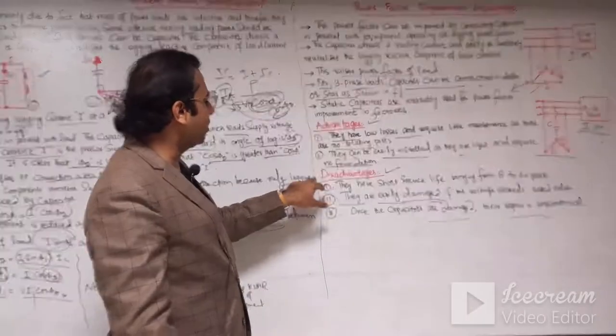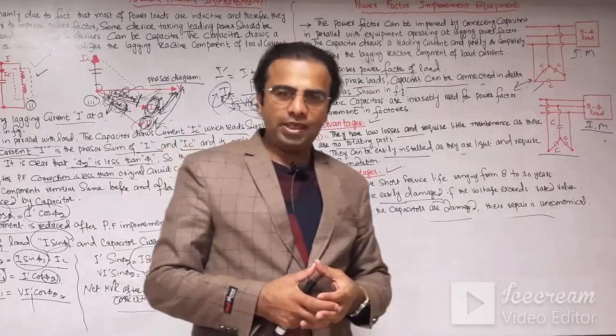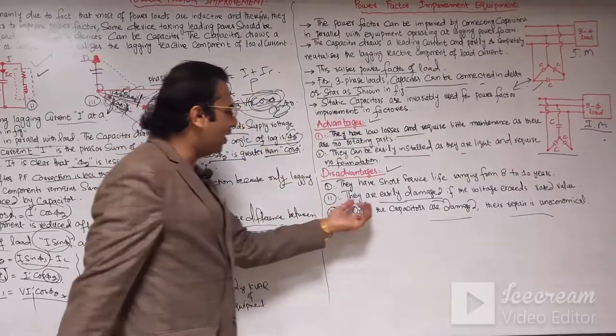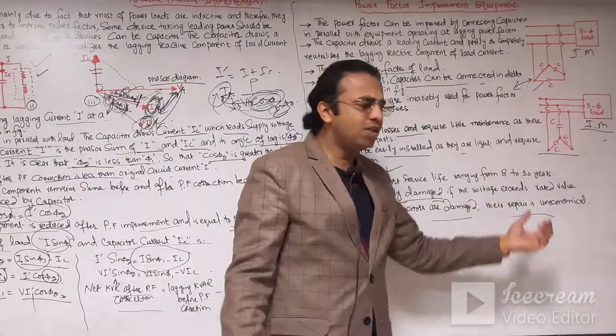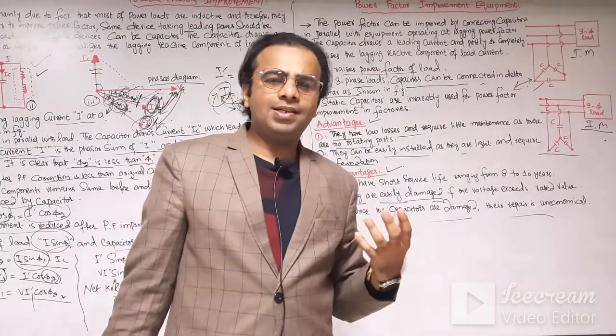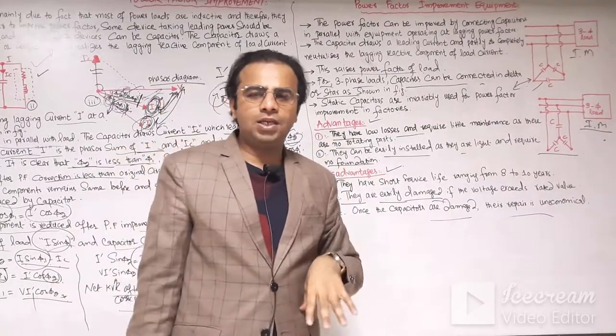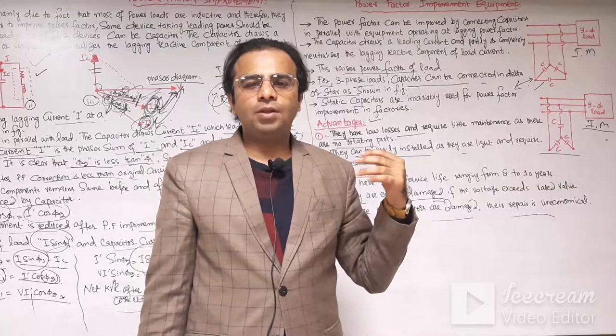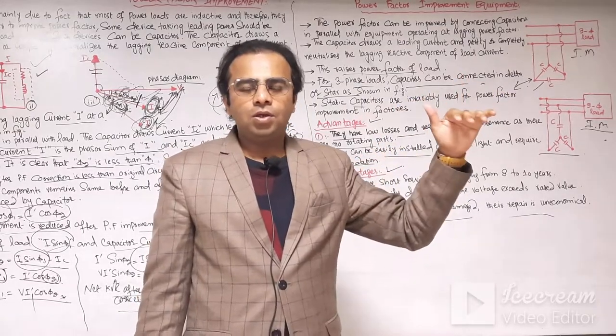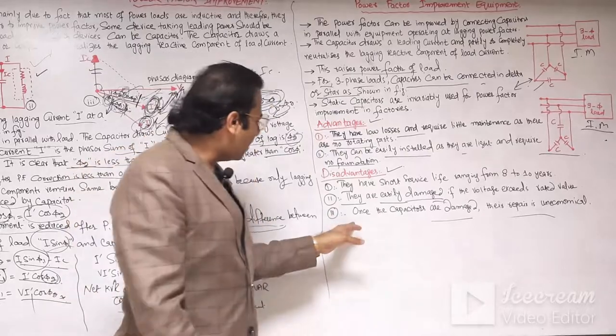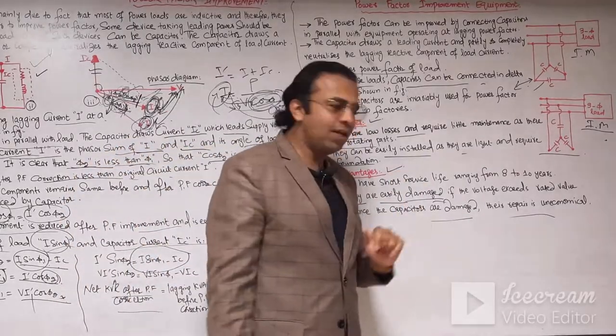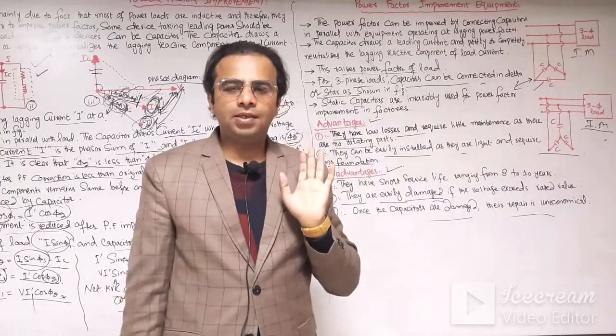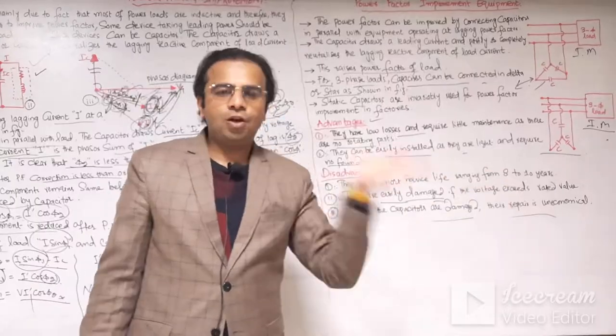The disadvantages of the static capacitor are: first, they have a short service life of 8 to 10 years. Second, they are easily damaged if the voltage exceeds the rated value — if an over-voltage condition occurs in the power system due to any abnormal condition, the capacitor can be easily damaged beyond the prescribed nominal value given by the manufacturer. Third, once capacitors are damaged, their repair is uneconomical and replacement is the only option.